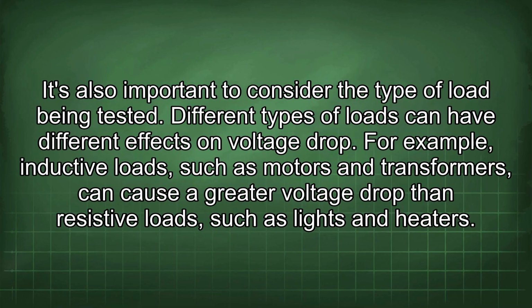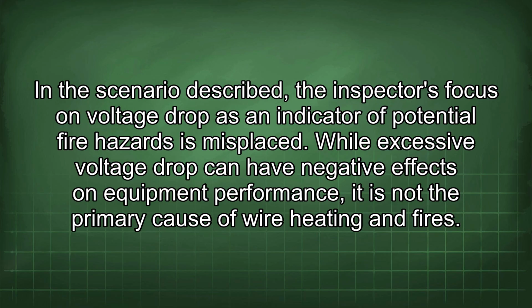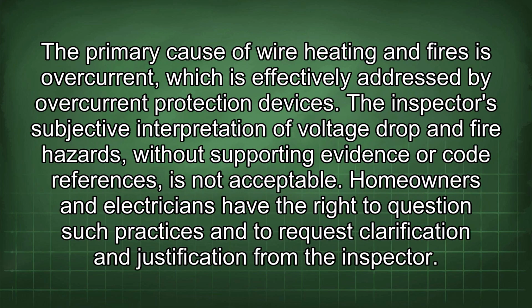It's also important to consider the type of load being tested. Different types of loads can have different effects on voltage drop. For example, inductive loads, such as motors and transformers, can cause a greater voltage drop than resistive loads, such as lights and heaters. In the scenario described, the inspector's focus on voltage drop as an indicator of potential fire hazards is misplaced. While excessive voltage drop can have negative effects on equipment performance, it is not the primary cause of wire heating and fires. The primary cause of wire heating and fires is overcurrent, which is effectively addressed by overcurrent protection devices. The inspector's subjective interpretation of voltage drop and fire hazards, without supporting evidence or code references, is not acceptable. Homeowners and electricians have the right to question such practices and to request clarification and justification from the inspector.